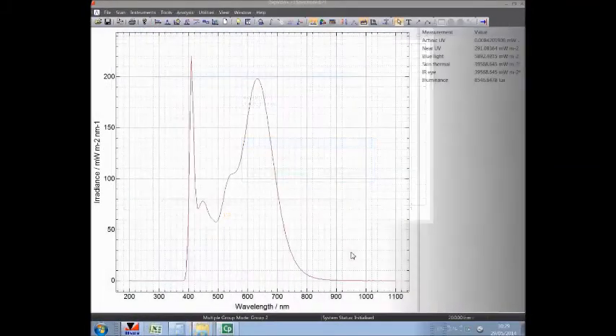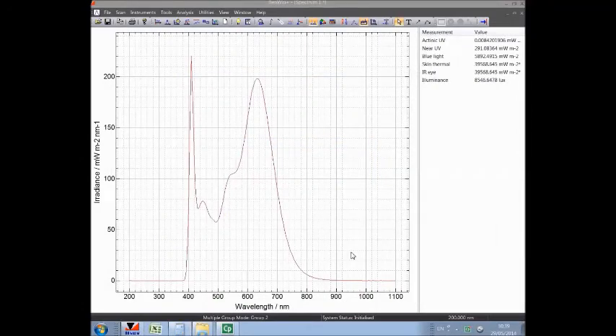And we can see now that on the y-axis, irradiance in milliwatts per meter squared per nanometer is now shown because calibration is applied, and we are returning the absolute irradiance of the source. And we will pick this up at the end of the measurement. Now, at the end of the measurement, we can see the measurement result. The absolute irradiance produced by this source at 200 millimeters from the source, here showing this 405 nanometer LED pumping a phosphor. It's an unusual technology.